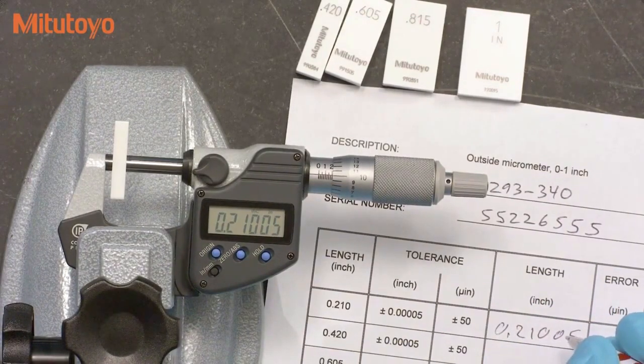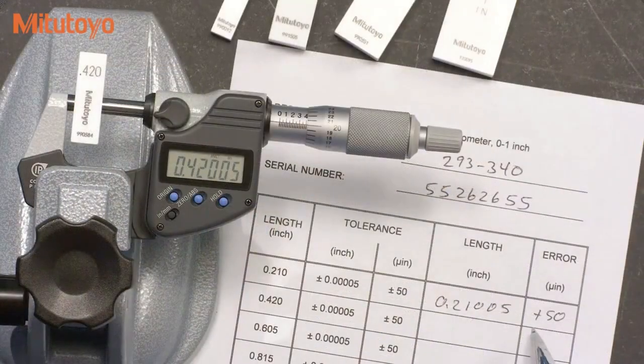To be more efficient, it is often useful to not record the entire measured value, but just the observed error. This digital micrometer, in inches, has a 50 millionths resolution, and so the readings will be something like 0, plus 50, as in this case, or minus 50 millionths. In metric, the errors will be something like 0, 1, or minus 1 microns.